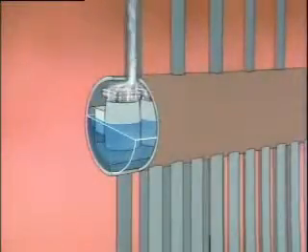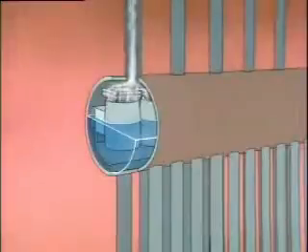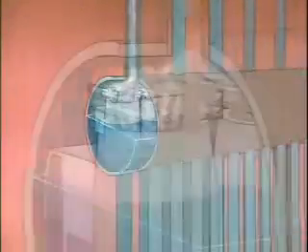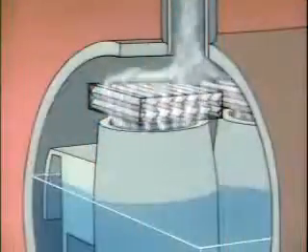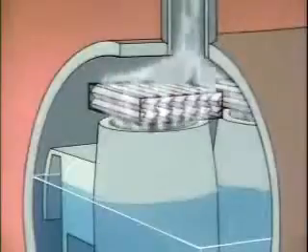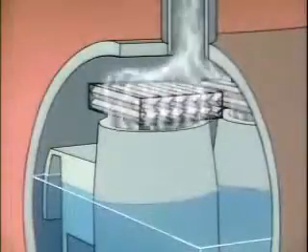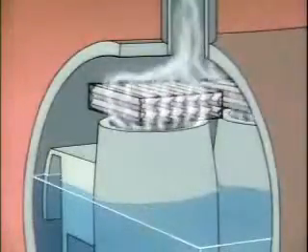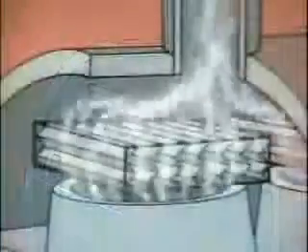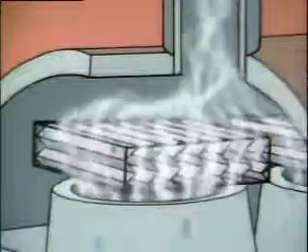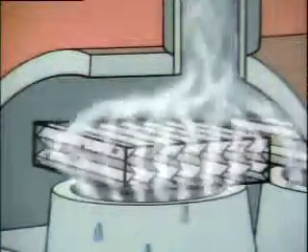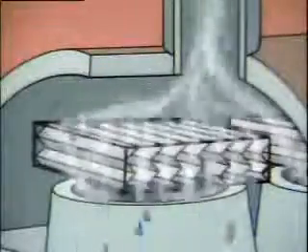A steam dryer is often found in processes where extremely dry steam is required. The dryer consists of a series of V-shaped plates; as steam flows through them it must make several changes in direction. Water droplets can't change direction as easily as the steam, so most droplets separate and drip back into the drum while the dry steam flows through the dryer and on to the plant.